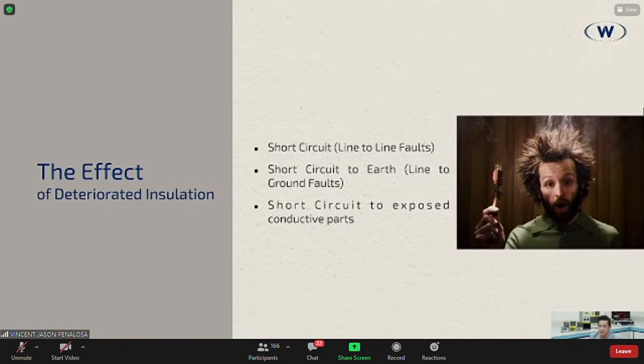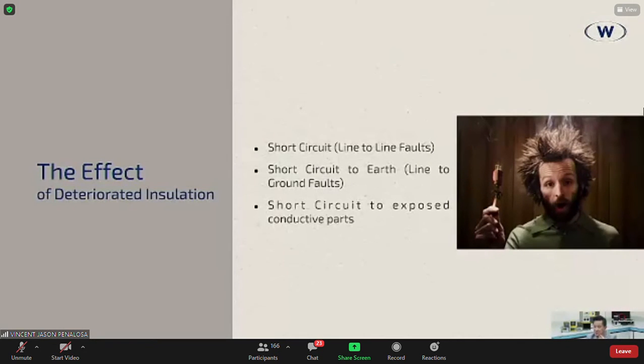No, we hear this a lot. We hear short circuits. A lot of times it doesn't really happen, not too much. No. Then you have short circuits to earth or line to ground faults. If you are on an ungrounded system and leakage capacitance is not that high, chances are it's not going to trip right away. Perfect example are the ones in DC systems. You know, you have a hard fault to ground, it just keeps on running. However, there will be a voltage shift to ground. No? And then you have the short circuit to expose conductive parts. This is something more capacitive in nature, and we will be discussing leakage capacitance as we go along.